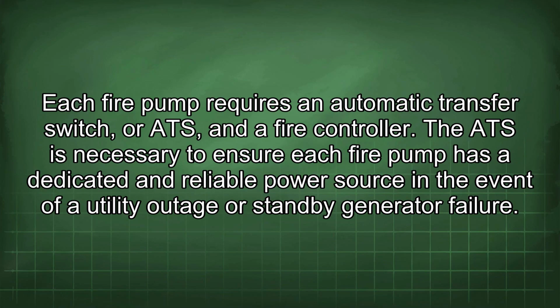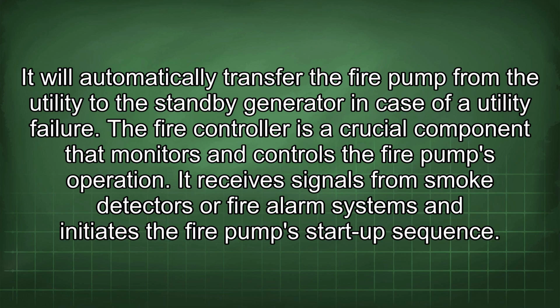Each fire pump requires an automatic transfer switch, or ATS, and a fire controller. The ATS is necessary to ensure each fire pump has a dedicated and reliable power source in the event of a utility outage or standby generator failure. It will automatically transfer the fire pump from the utility to the standby generator in case of a utility failure.